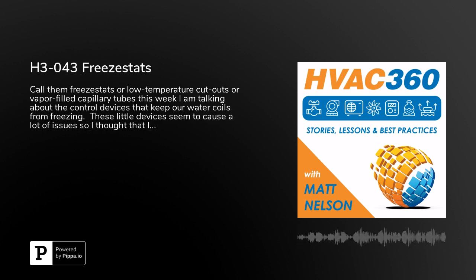So typically there are going to be two types of these freezestats: the manual reset and the automatic reset. Now, I'm a big fan of the manual reset, because that kind of mandates that the operator gets off his duff and goes to check on the unit itself. So if something went wrong and the unit tripped off, they're there to say, okay, I see the reason, let's correct it, and then they'll reset the unit and let it go on its merry way.